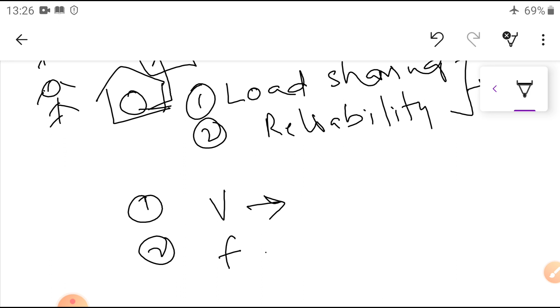What is the first point again? The terminal voltage of the incoming alternator must be equal to the busbar voltage, within at least plus or minus 10%.